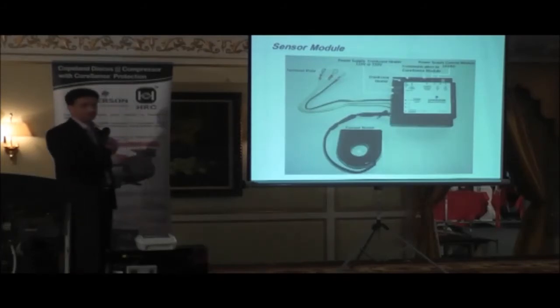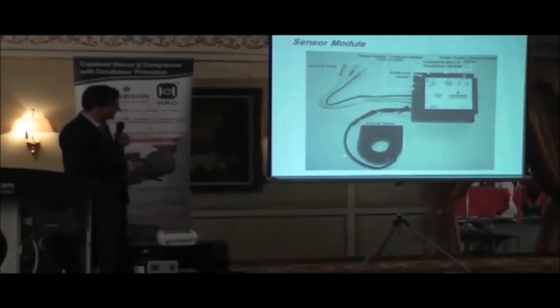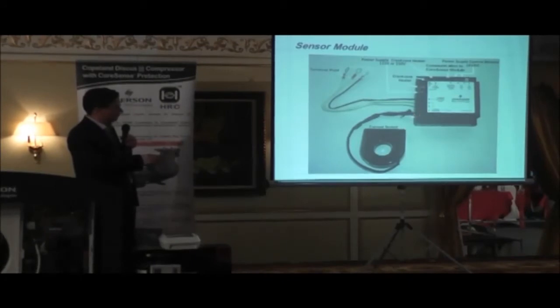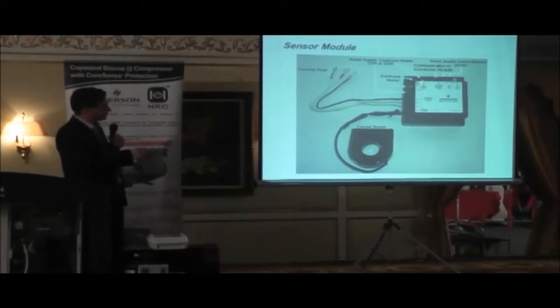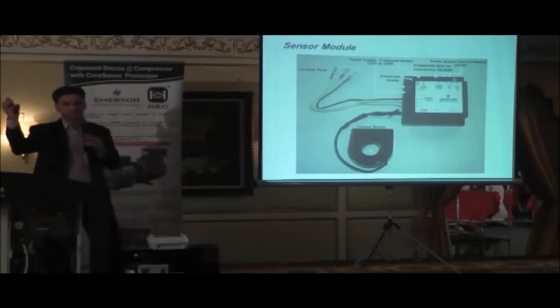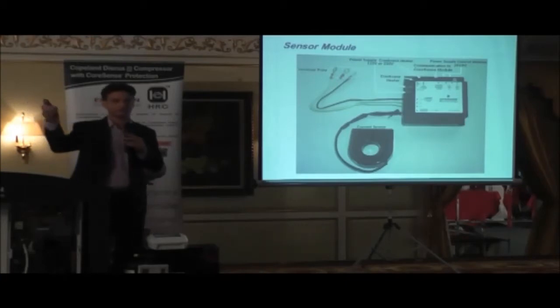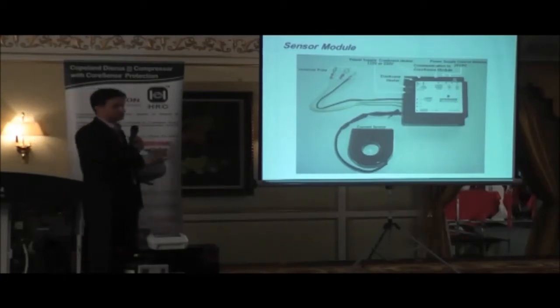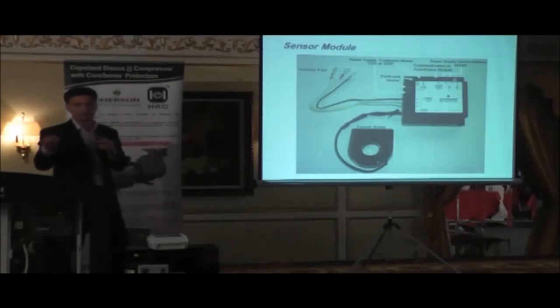So you get, this is a close-up of the sensor module. This is the current sensor. It's connected via a 4-pin plug to the sensor module. The sensor module itself will have 3 wires connected to L1, L2, L3. These 3 wires are going to be checking voltage, low voltage, voltage imbalance, missing phase. Okay?